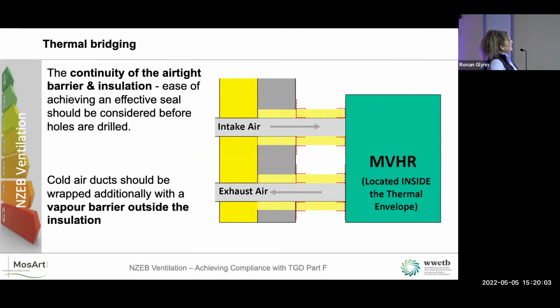So thermal bridging, when you consider MVHR, so now we have it down inside our thermal envelope. So this is inside our house. This is our construction. It's, I don't know, cast concrete, block on flat, whatever it is. So if we have two ducts going in and out of our building, we're creating thermal bridges. So we have to have a look at that. We have to keep the continuity of the airtight barrier and the insulation.